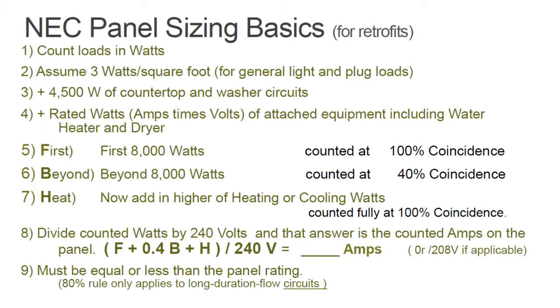Beyond that, the code looks at the rated watts on the nameplate of the attached equipment - things like water heaters, furnaces, heat pumps, but also the dryer and the range. What the code says is the first 8,000 watts of that equipment is counted at 100% coincidence, meaning at the time the building has its peak load, they've assumed the first 8,000 watts will be on.